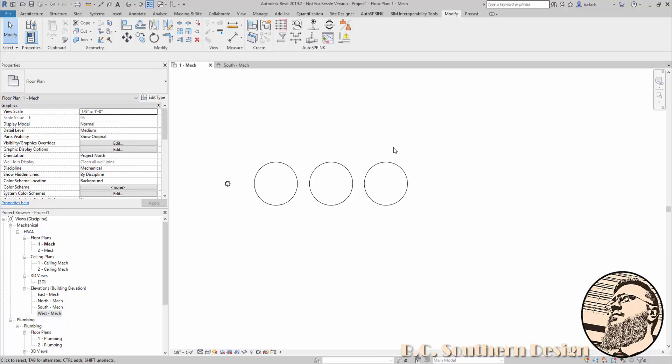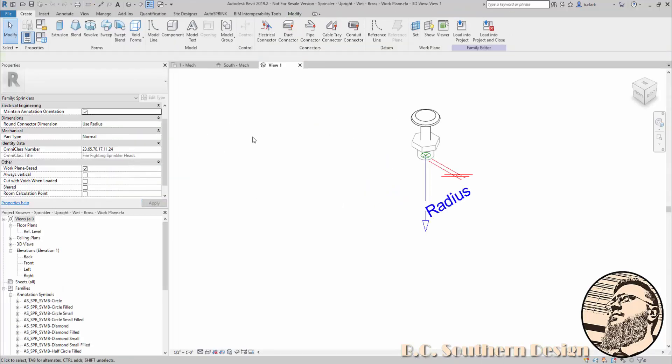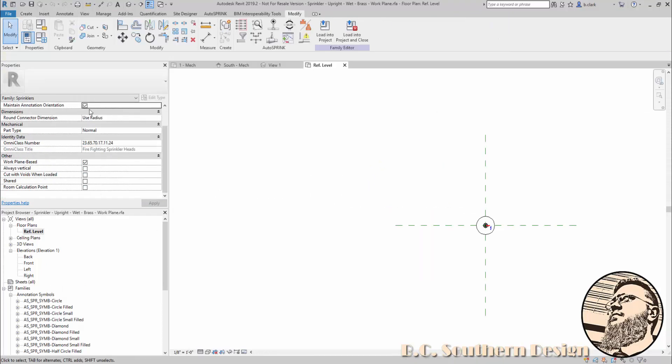but it's still oriented that symbol perpendicular to my view. So if you want your symbols to show up for your heads that are going along a slope, make sure that you have heads that can be associated with a workplane and that your symbol has maintain annotation orientation checked.